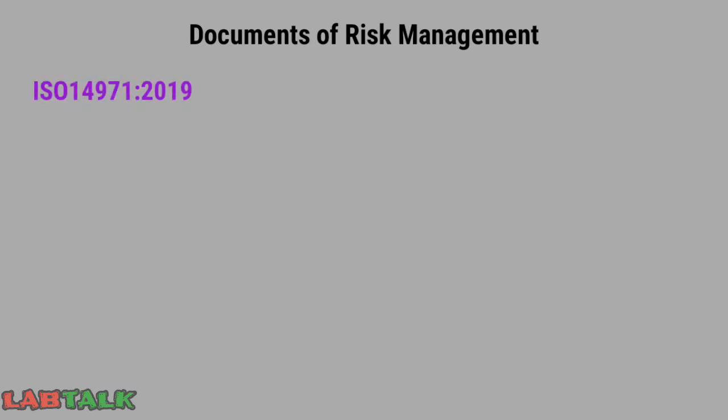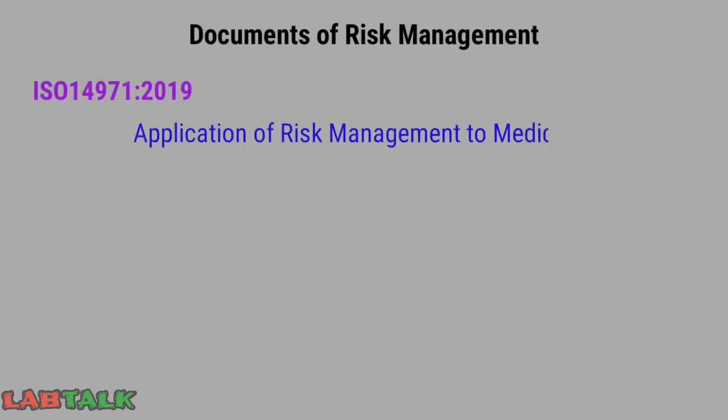The first document is ISO 14971:2019. This document deals with risk management in medical devices. It defines protocols, terminologies, and principles applicable to the risk management of medical devices, their software, and in vitro diagnostic devices. Essentially, this document is applicable to all equipment and devices in a healthcare setup.